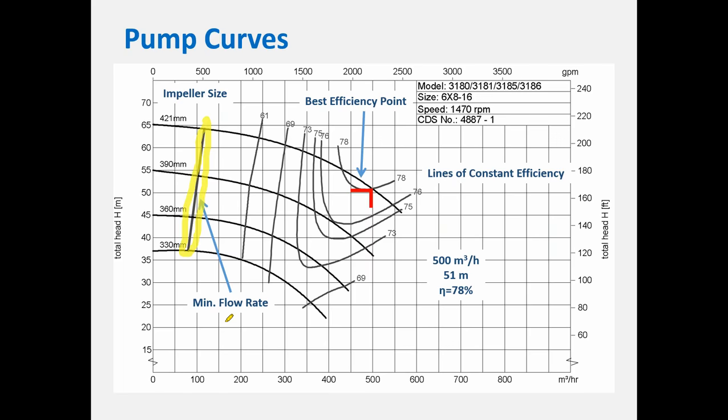The power formula is: Power = (density × g × H × Q) / pump efficiency, where density is the fluid density, g is gravity, H is the head delivered by the pump, and Q is the flow rate. Motor and transmission efficiency are excluded here to simplify, but you could also read power directly off the pump curve if that's available.